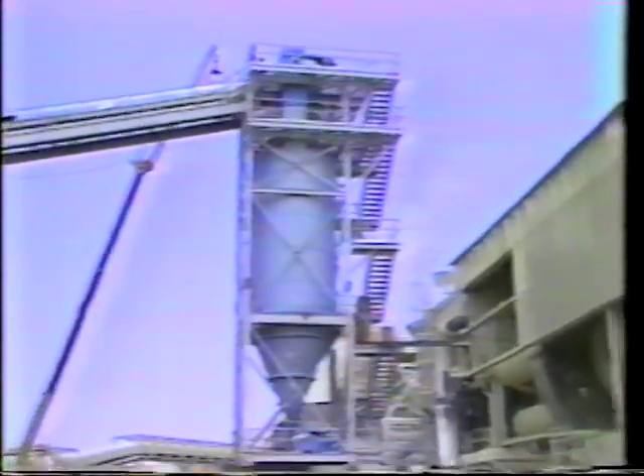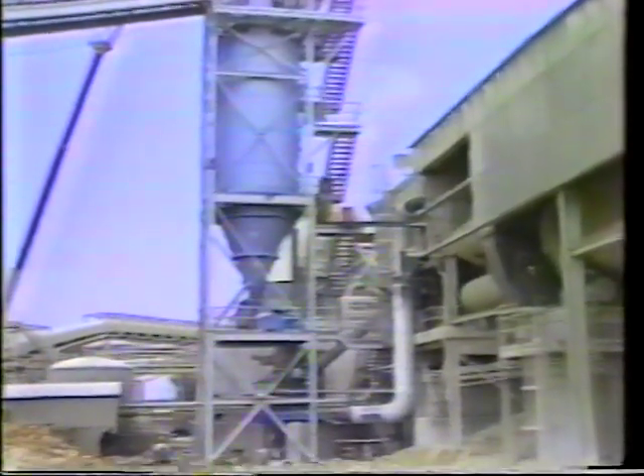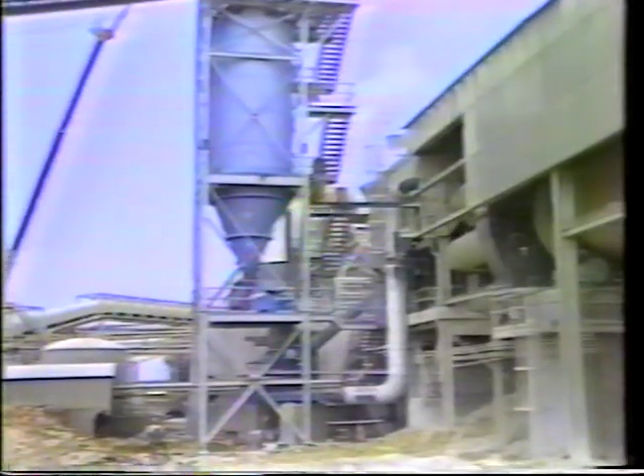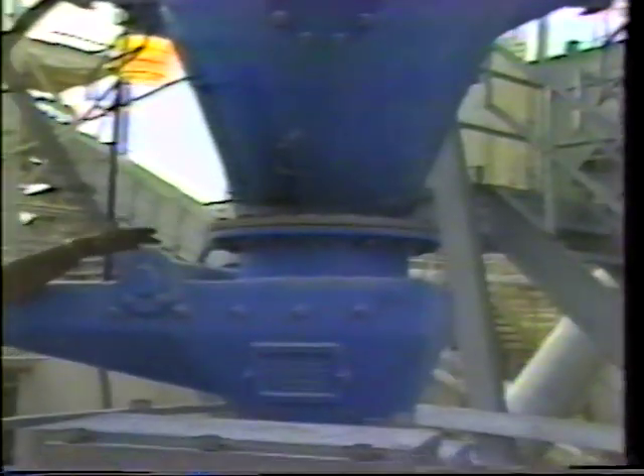A storage silo has been provided at the hot end of number 2 lime kiln that has a capacity of 123 tons. This is slightly in excess of the requirements for 1 day when burning maximum coke. The silo is 14 foot in diameter and a straight wall height of 25 feet. Load cells have been provided so the weight of the silo and hence its contents can be determined. The weight or indication of how much coke is in the silo will be determined on a control panel.